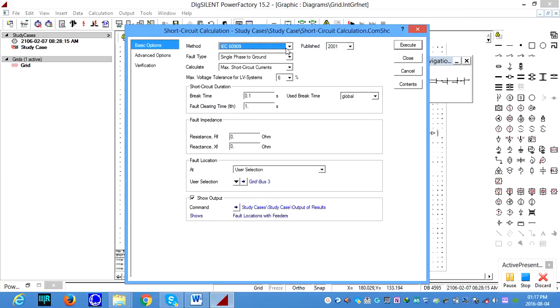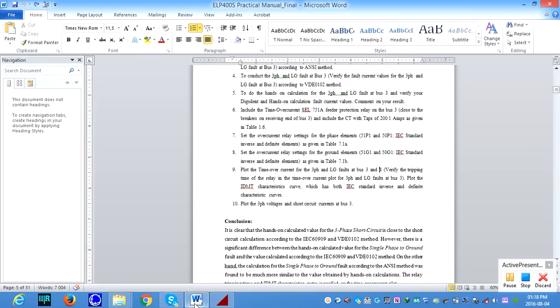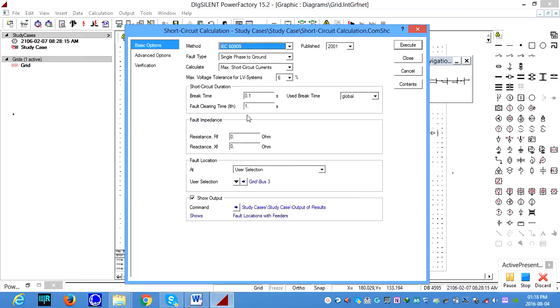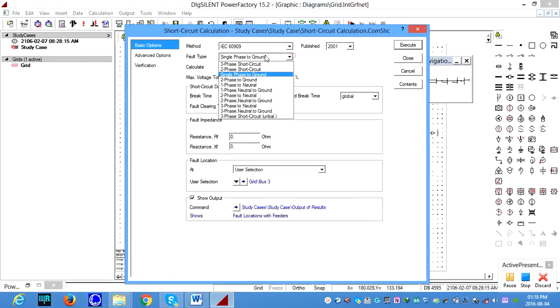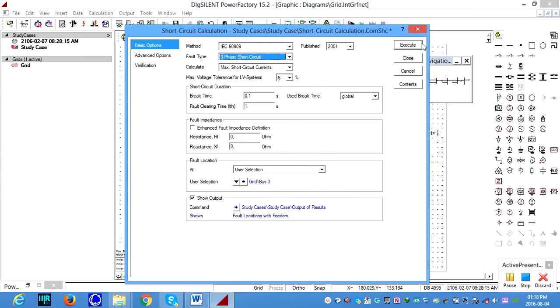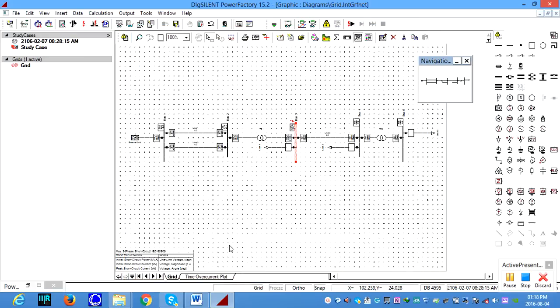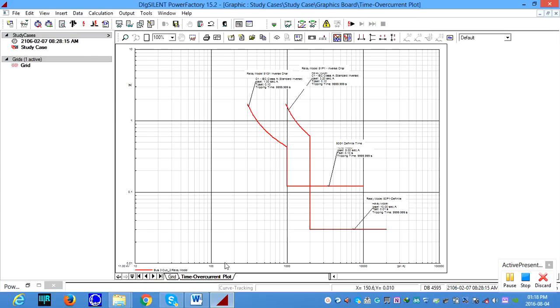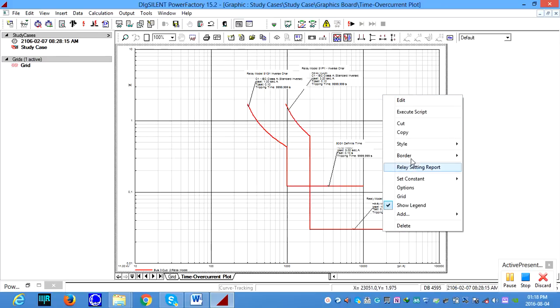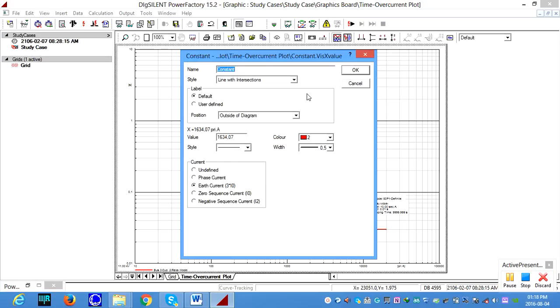You can apply at bus 3, calculate a short circuit. Okay. Let's use whatever method they specified. You can use any method, it doesn't matter. So I am just using three-phase short circuit, IEC method, execute, and you need to go to here. Okay, and we also want to set the constant, that is the x values. Okay, we can say fault current magnitude.